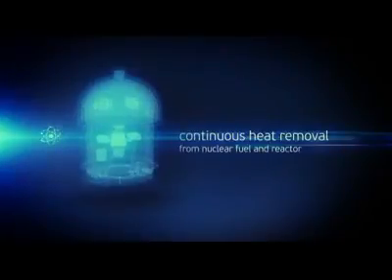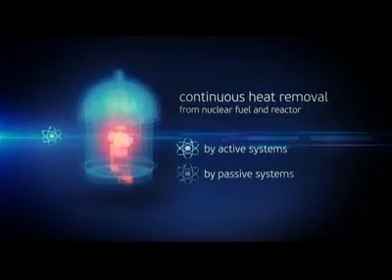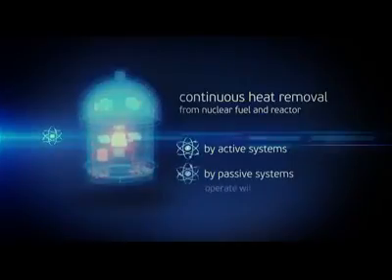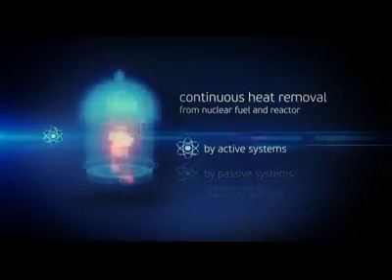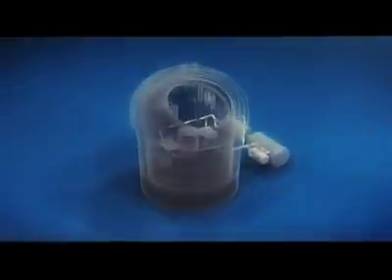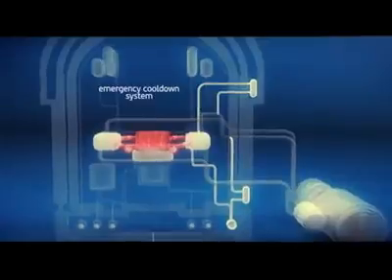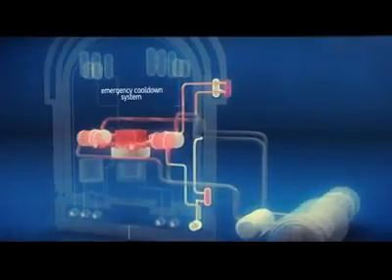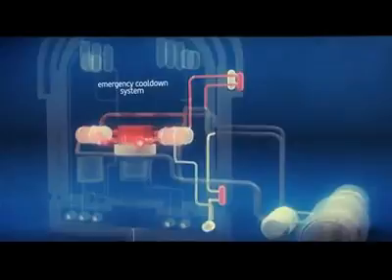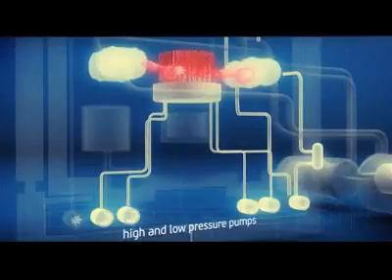The second task — continuous heat removal from nuclear fuel and reactor — is solved by combinations of active and passive safety systems. A key difference between them is that passive safety systems operate without electricity and without involvement of personnel. In the active system, if the reactor cooling circuit remains integral, the reactor is cooled by the emergency cool-down system, where heat is removed via the secondary circuit. In the steam generator, residual heat is transferred to the secondary water and then to service water. In case the primary circuit is damaged, high and low pressure pumps are actuated to ensure continuous water supply to cool the reactor, drawing water from the spent fuel hold-up pond within the containment and from the containment sump.